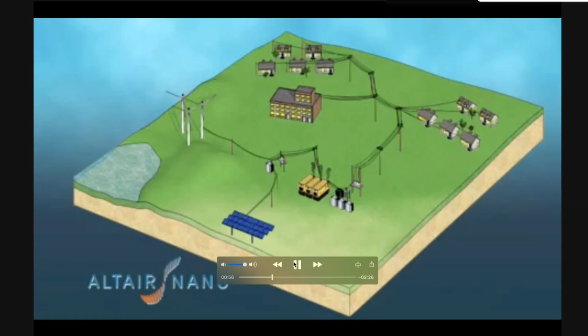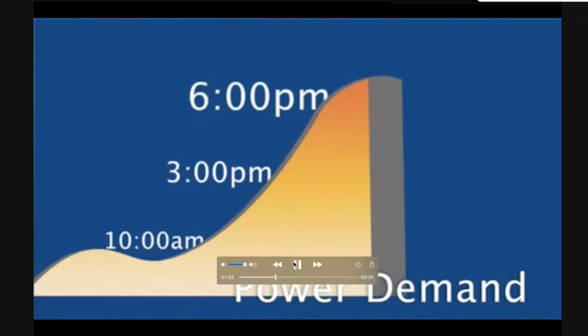In some microgrids, integration of renewable energy, such as wind and solar arrays, are used in combination with diesel generators. However, because they are limited in capacity to generate energy, microgrids are susceptible to potential inefficiencies that include high fuel consumption and reliability issues. Microgrids must continually manage fluctuations in demand and generation to maintain a 60 Hz frequency, which is a requirement for maintaining grid stability. Interruptions in this frequency can lead to power quality issues that can result in brownouts and, in some cases, even blackouts. To regulate frequency, it is estimated that 10% of total generation capacity must be reserved for managing fluctuations in demand and generation.